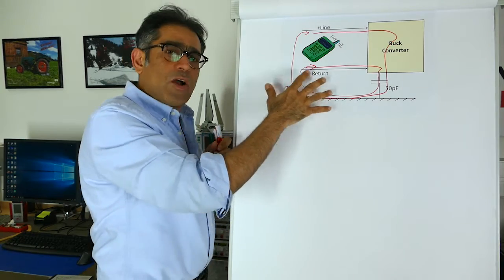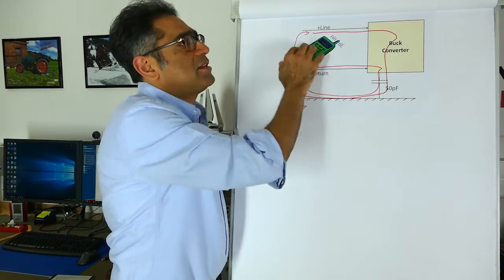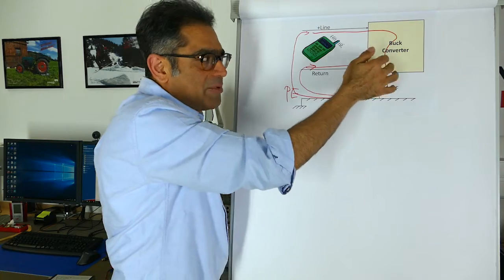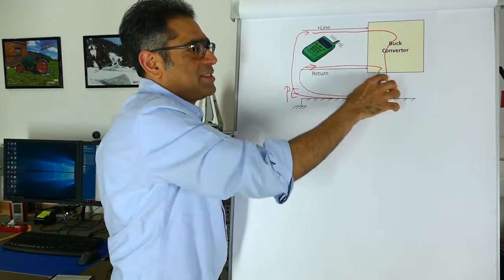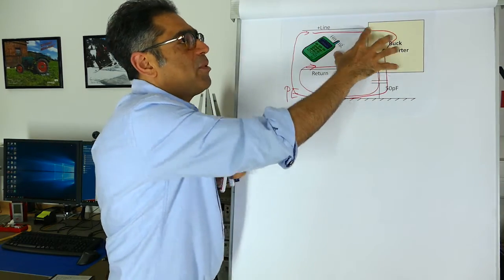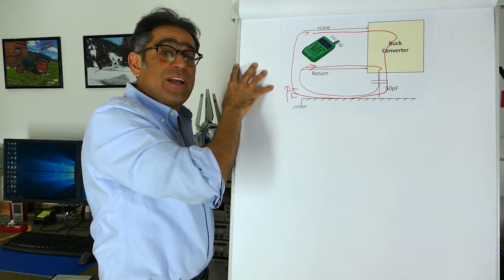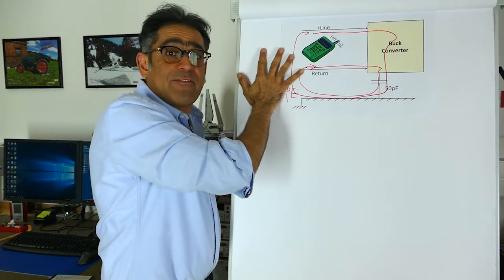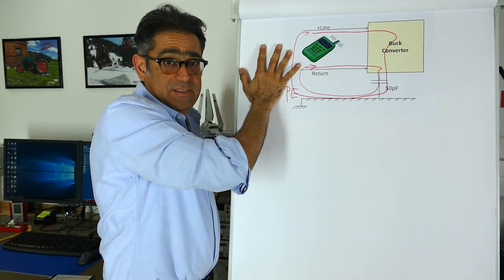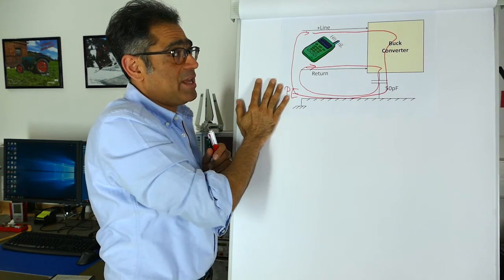And these are common mode currents—the currents that couple via some capacitance between the body and the chassis and then return. The problem with these is that this loop is actually much larger, and therefore you may have conducted emissions test failures when you go to the EMC test chamber.